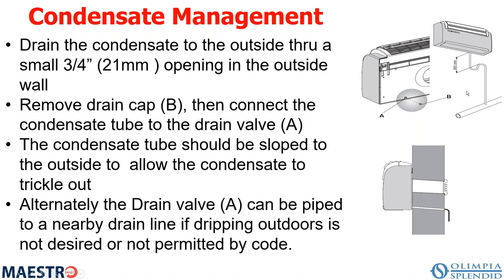drip outside. Or if you have access to a drain in the wall or in the house, then you put a little trap on there, so water remains in it and you don't get fumes that back up. But either way is acceptable. Now, the third option for some people: in the units that we saw at the very beginning that were on the wall, you saw the outside facades of the buildings. There were no drains in any of those because their temperatures in the summer aren't humid enough to cause them to do anything but evaporate that water. And in the wintertime, they don't have enough moisture that it builds up and has to defrost on a very regular basis. So they will actually leave both plugs in the unit.